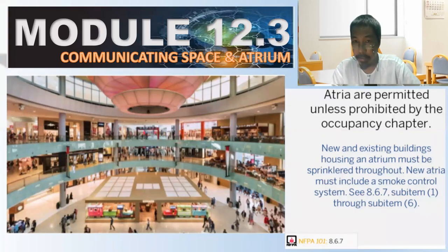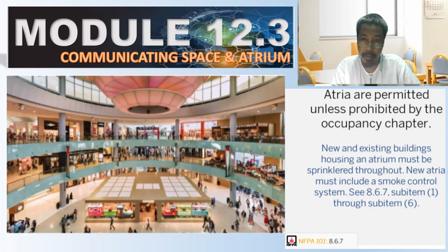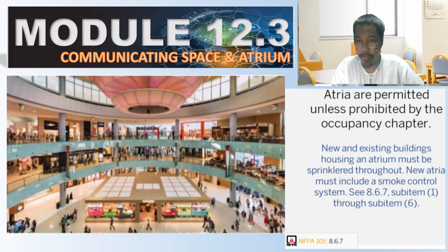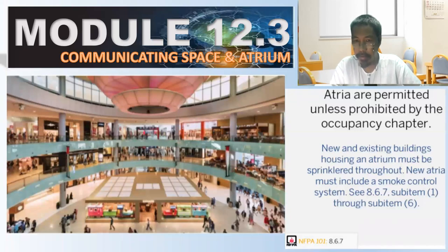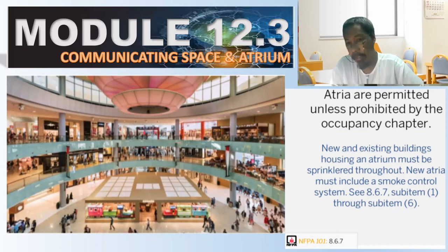Atria are permitted unless prohibited by the occupancy chapter. Note that 'atria' is the plural form of 'atrium,' though 'atriums' is also commonly used. In a new building housing an atrium, it must be sprinklered throughout — the word is 'must.' Also, new atria must include a smoke control system.